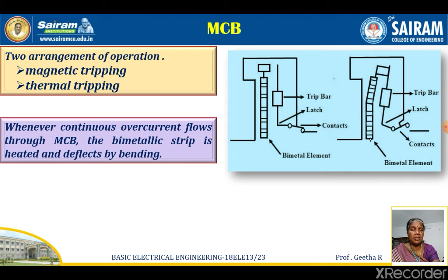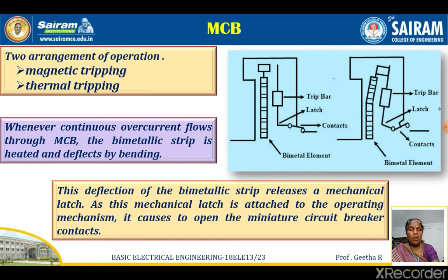since it is moving its position, you can see here the trip bar is moving accordingly. The contact is open now, so the circuit is in off position, or you can say the MCB is in off position, thus discontinuing the circuit or discontinuing the supply. So this deflection of the bimetallic strip releases the mechanical latch. As this mechanical latch is attached to the operating mechanism, it causes the miniature circuit breaker contacts to open.